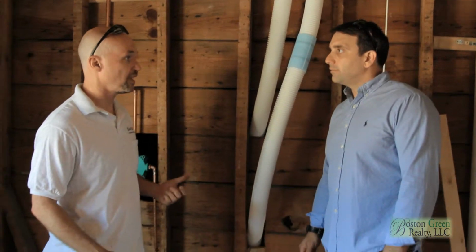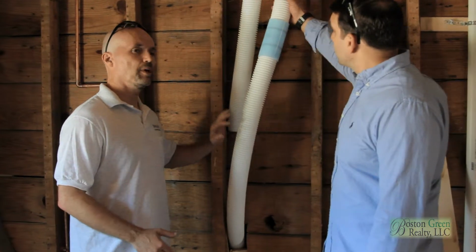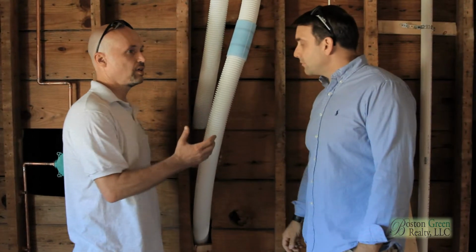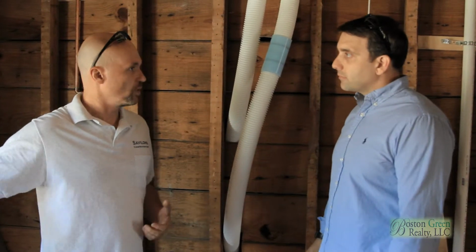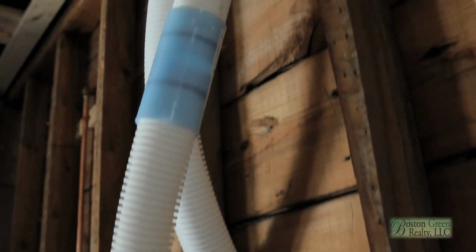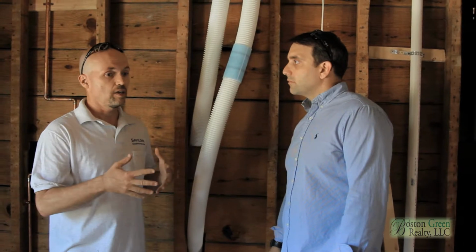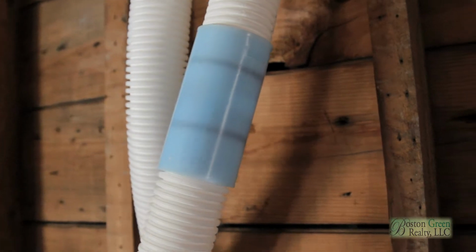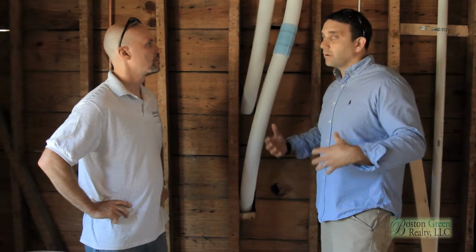So when we're getting the house this tight, we really have to start thinking about air quality. In a deep energy retrofit, you're actually going to have better air quality than you would in any conventional house, because we're providing outside air, fresh air, where we take it from a point furthest away from any known air pollution sources, the road, the driveway where you might have an engine running. So we're bringing in fresh air, we're exhausting stale air, and we're running through a heat exchanger where we capture that waste energy and raise the incoming air temperature, if it's wintertime, to something pretty close to the outgoing ambient temperature. And if those have chemical sensitivities, this could be something that helps create an environment that they can breathe in.